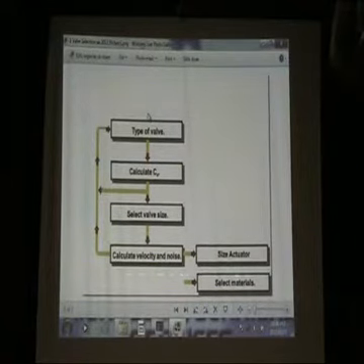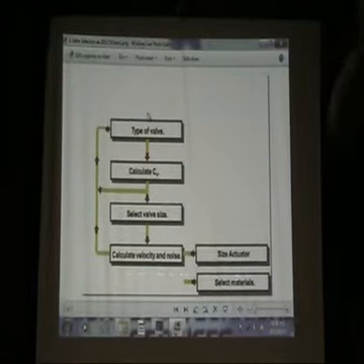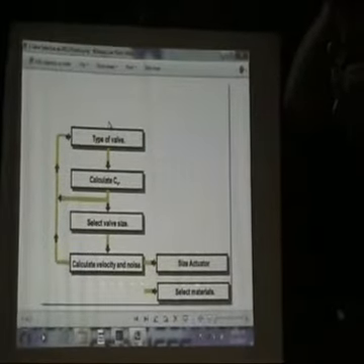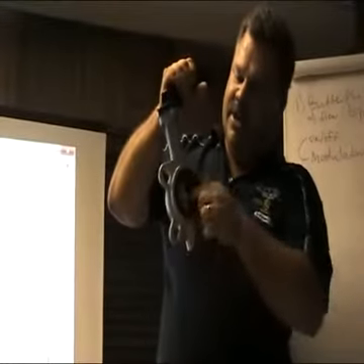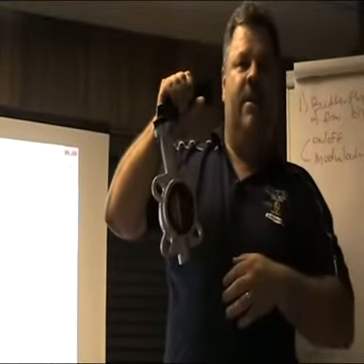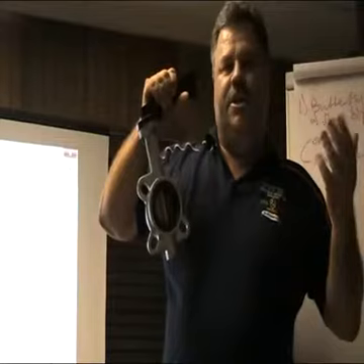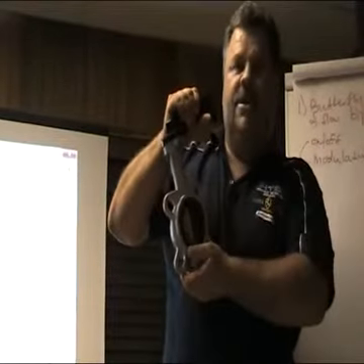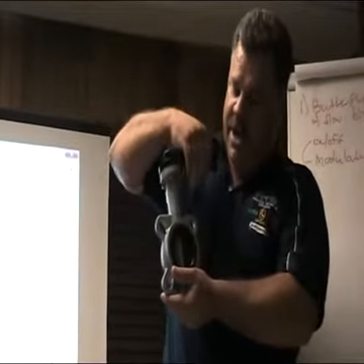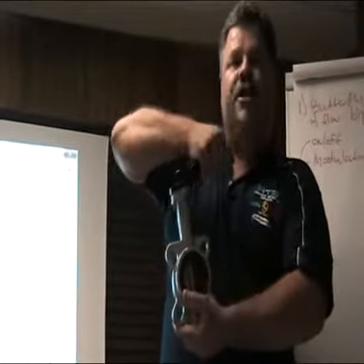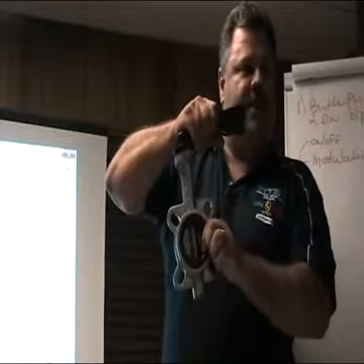You know this disc, yeah? It's in the center of the valve. The moment they tighten this, the liner deforms around this disc, and the moment they open the valve, the disc breaks this liner. So the plant hasn't even started up and it has sheared already. It's broken. So what they should do is, I don't know if I'm answering that question, but this is what I've experienced. When they've installed this, they should open this and then tighten it.